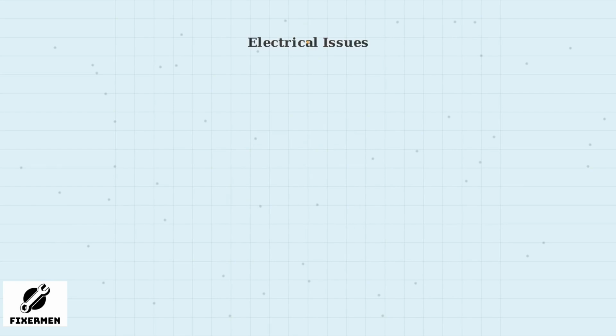Third, electrical problems such as voltage fluctuations or faulty wiring cause the compressor to overwork, generating excess heat and triggering the E4 protection mechanism. Addressing these underlying root causes, whether refrigerant imbalance, airflow restrictions, or electrical faults, is essential for a lasting fix and preventing repeated E4 errors.